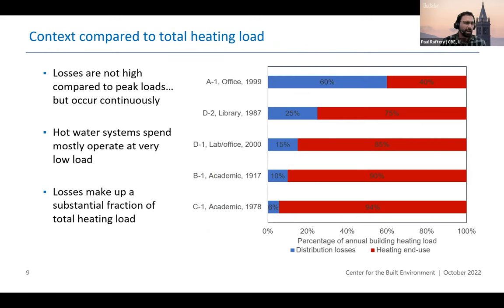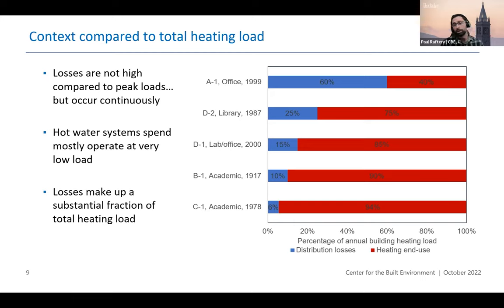The losses aren't high — 0.4 BTUs per hour per square foot is a tiny fraction of the peak design load for the heating hot water plant, which would typically be somewhere between 10 and 30 BTUs per hour per square foot in relatively mild climates. The big difference, though, is that these losses occur continually. Every time that system is at temperature, they're happening all the time. And we know that heating hot water systems operate at very low loads for the vast majority of the time — it's exceptionally rare to hit that peak load profile. So though the losses are low, because they're continuous, they can make up a substantial portion of the annual heating load on your heating plant.